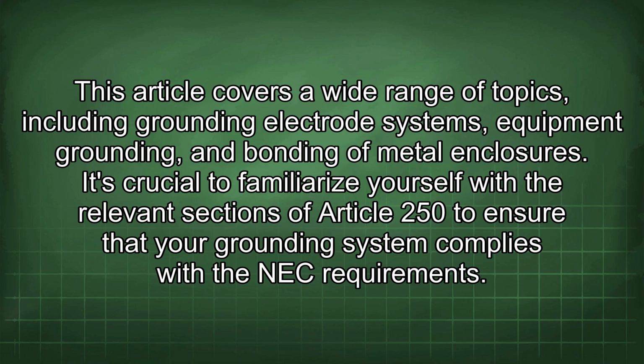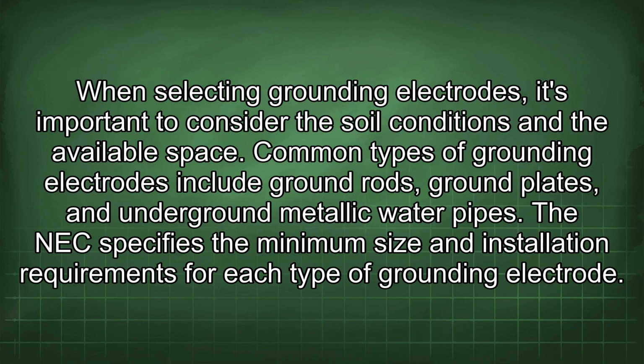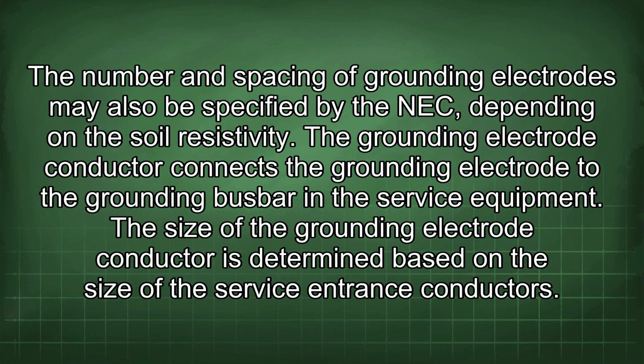the NEC requirements. When selecting grounding electrodes, it's important to consider the soil conditions and the available space. Common types of grounding electrodes include ground rods, ground plates, and underground metallic water pipes. The NEC specifies the minimum size and installation requirements for each type of grounding electrode. The number and spacing of grounding electrodes may also be specified by the NEC depending on the soil resistivity.